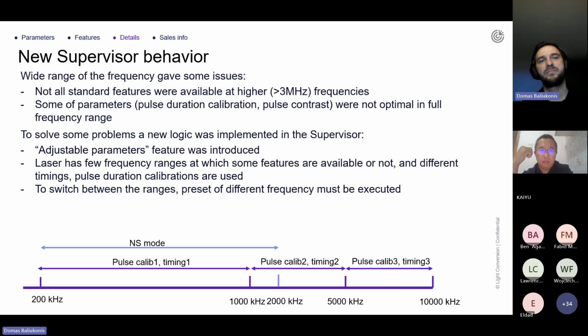So if you are working at a certain point of the frequency, different laser parameters, different timings, and different pulse calibration tables are applied inside the laser. This is a new behavior for our lasers, applicable only for this 10 megahertz model. To jump between those different frequency ranges, we need to apply a different preset.